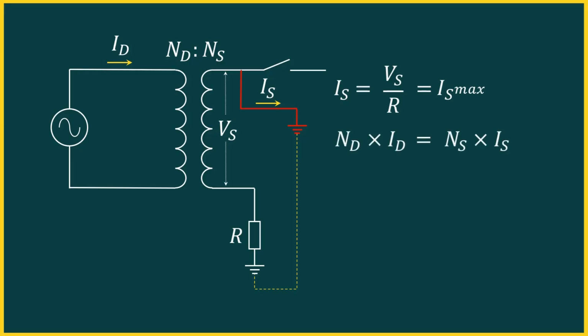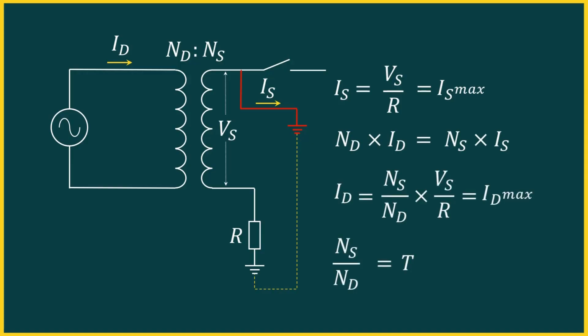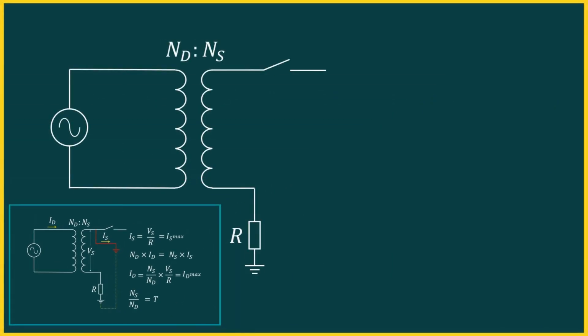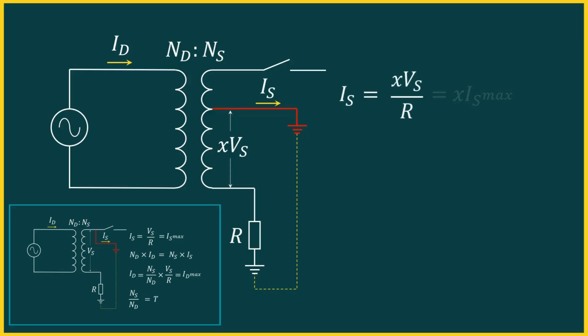This is the maximum earth fault current in the star winding. To find the delta side current, we can apply ampere turn balance, and hence the delta side current will be turns ratio multiplied by Vs upon R. And this is the maximum delta side current for an earth fault on the star winding. Now imagine that instead of a terminal fault, an earth fault occurs somewhere in the middle of the winding. The voltage behind the fault is X times Vs, where X represents the fault point from the neutral. The value of X will be 0 for a fault at the neutral and 1 for a fault at the terminal. So in this case, star side current will be X times Vs upon R.